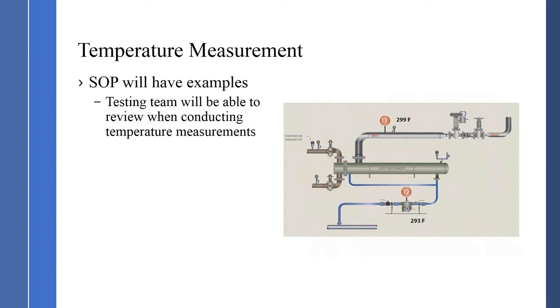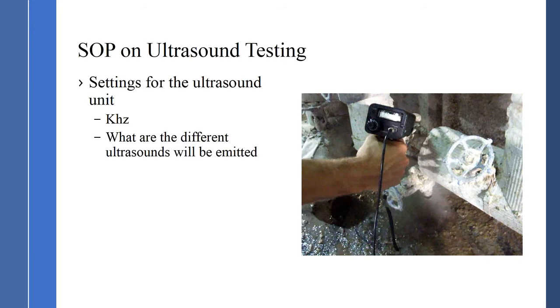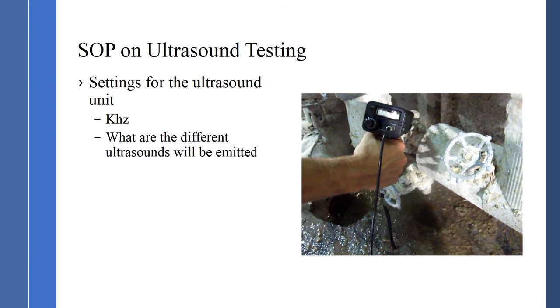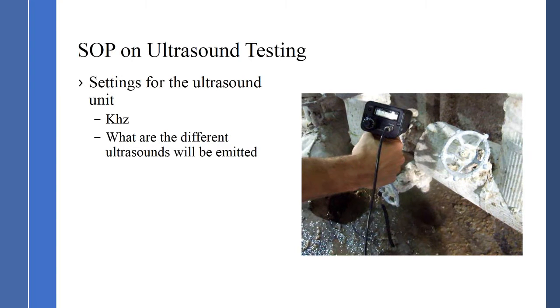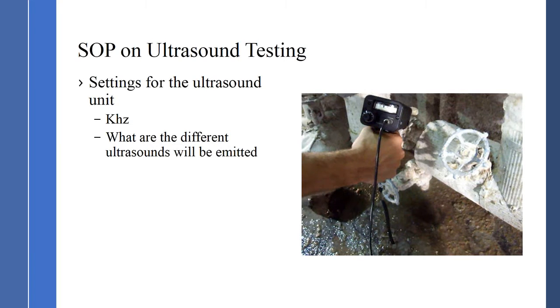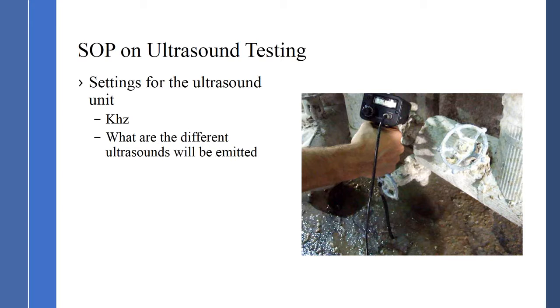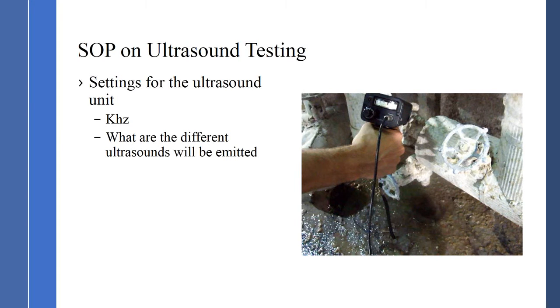The next section covers the settings of the ultrasonic unit — what kilohertz setting to use — and how to adjust the sensitivity of the ultrasonic units. It also covers the operation of the different types of steam traps. There are three major groups of steam traps: mechanical, thermodynamic, and thermostatic. We need to make sure people understand the testing procedures for each of those three groups.